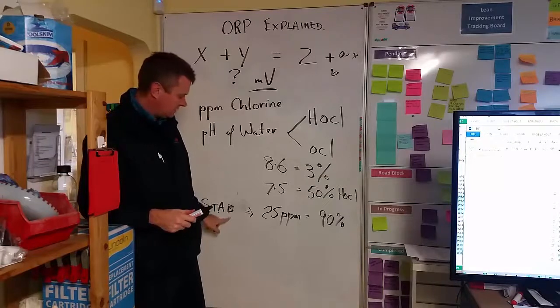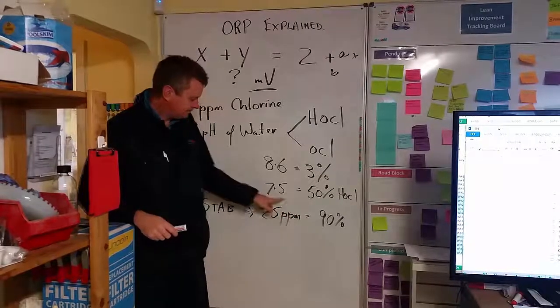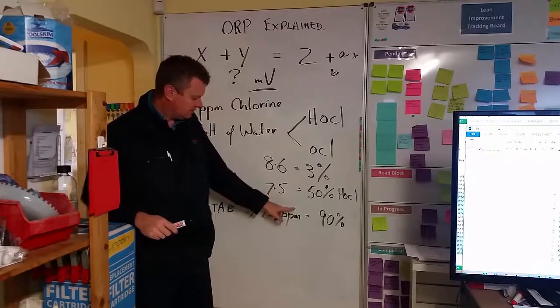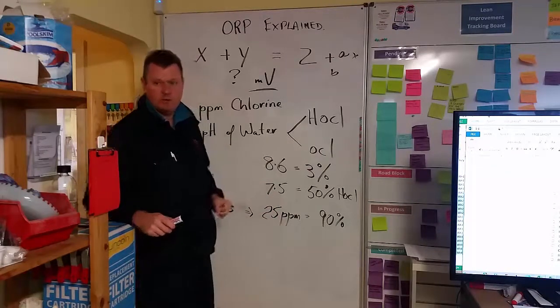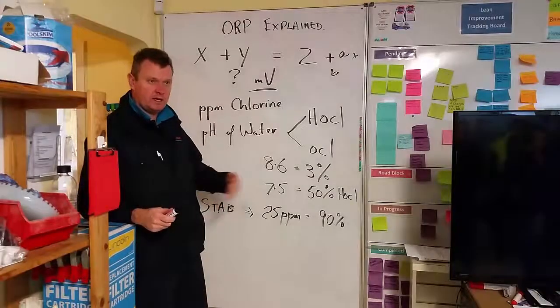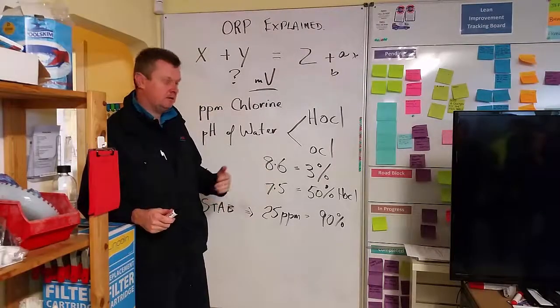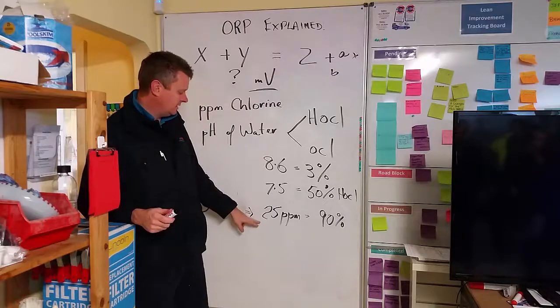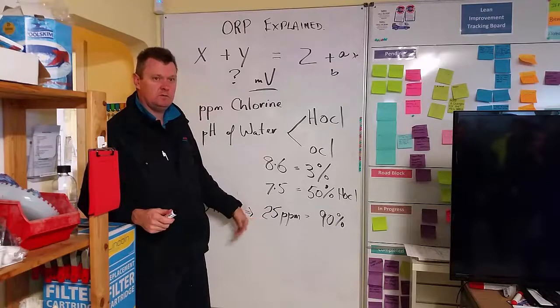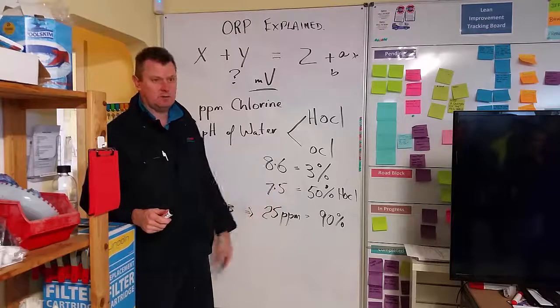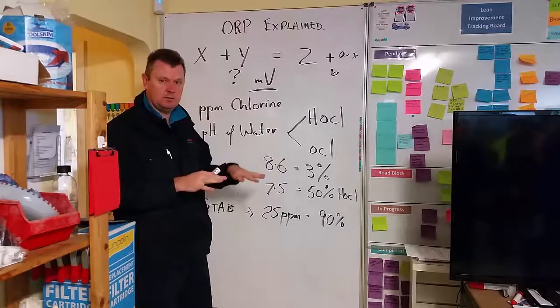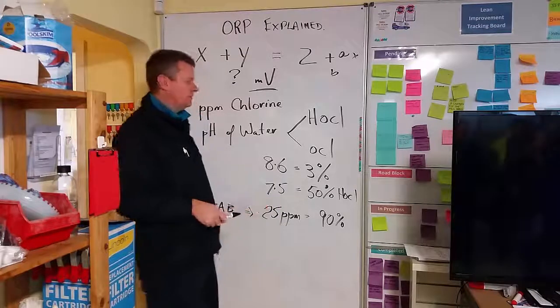But as I say, we should be looking at around about 35 ppm, I'd say, for our regular customers, because we're back there every month at least. Maintain 35, and then when you come to dose, if it gets down to 25, 500 grams or something like that to try and keep that stabiliser level at the lower end of the range.